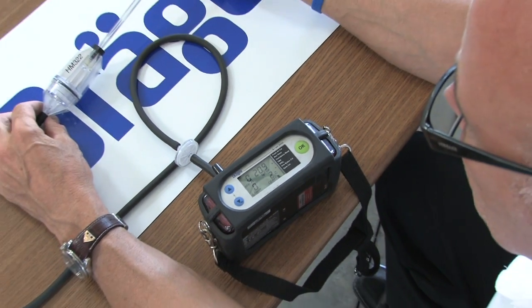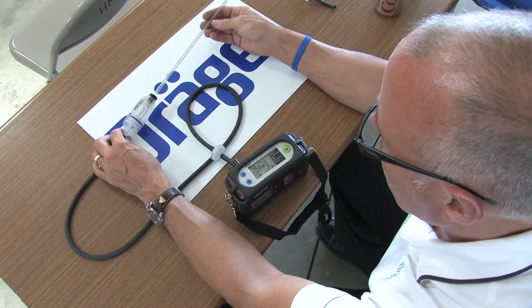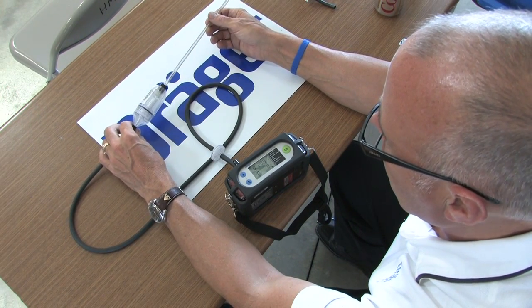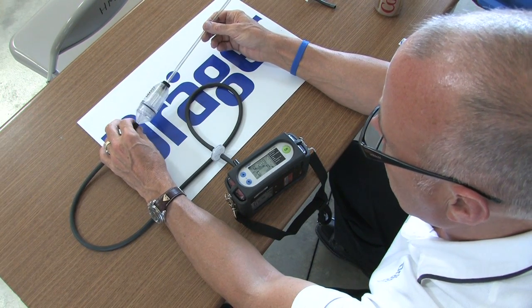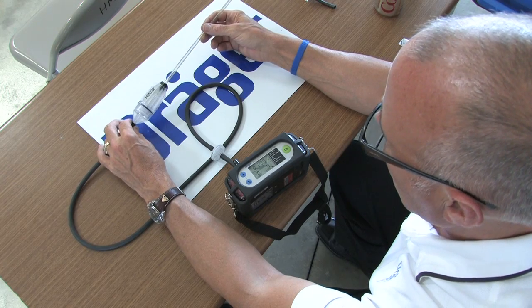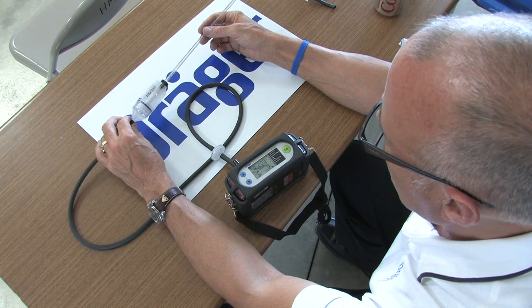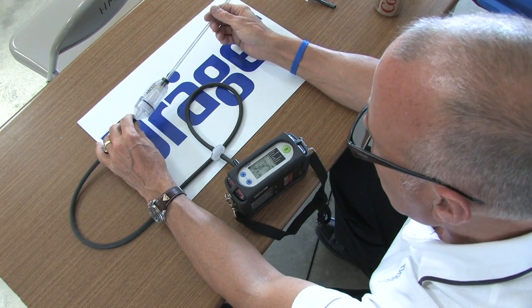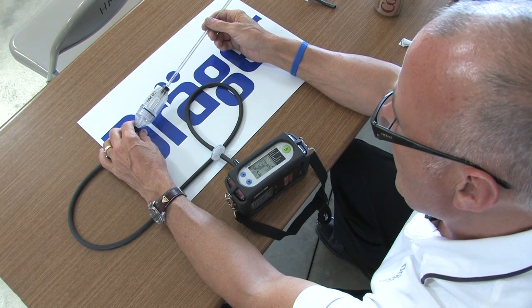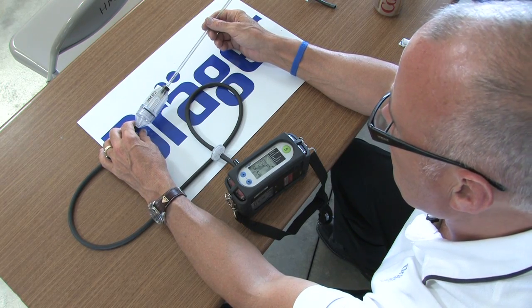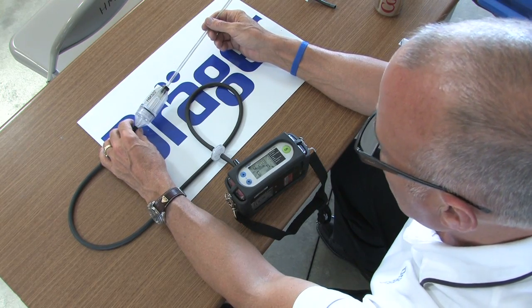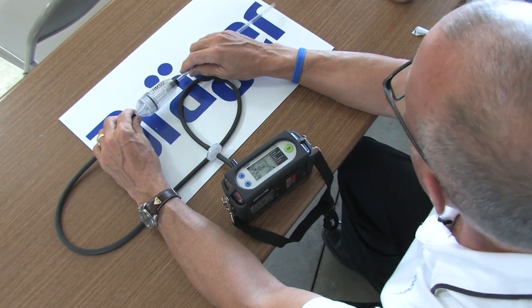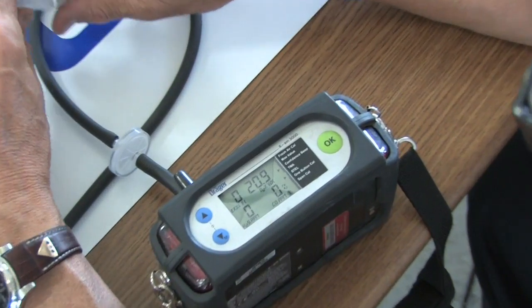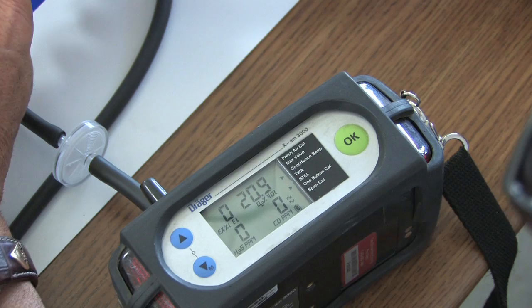And the CO will take a little bit of time to get back down to zero. But I can actually now, after I've done a bump test on the meter, my battery is good. I've checked the pump on the meter. We're back at zeros and 20.9. I can now use this instrument to go out and monitor in the field. However, one thing I would like to do before that is I'm going to calibrate this meter.